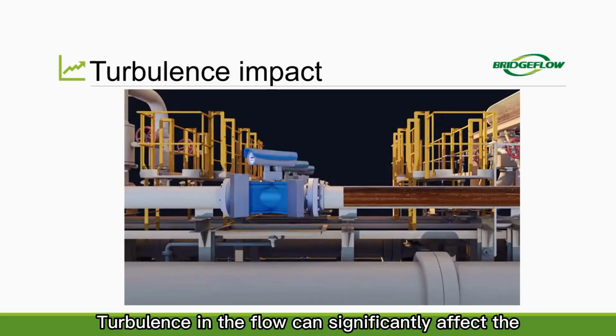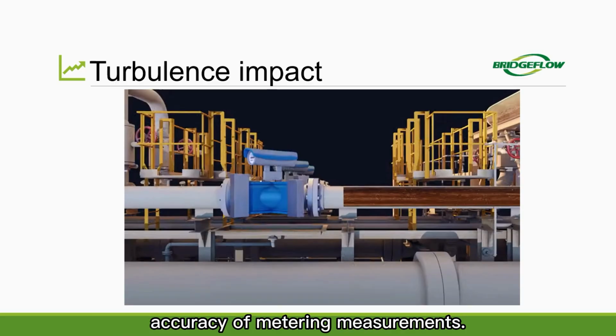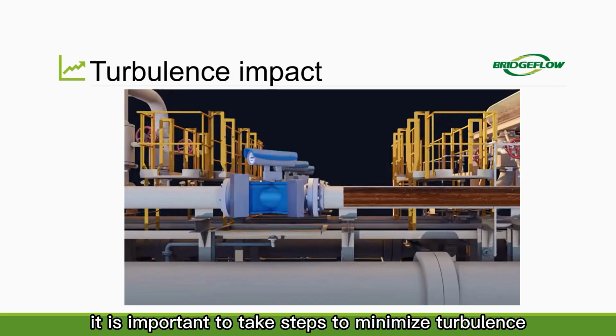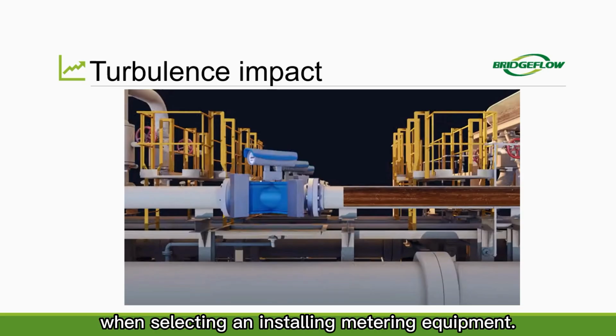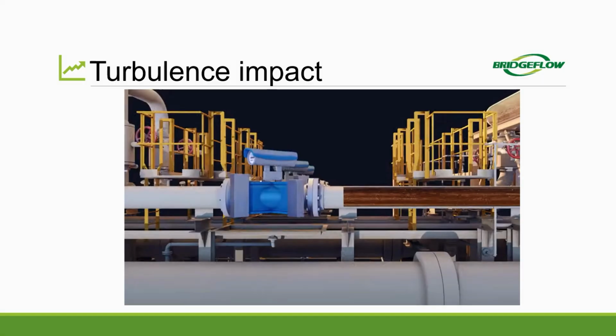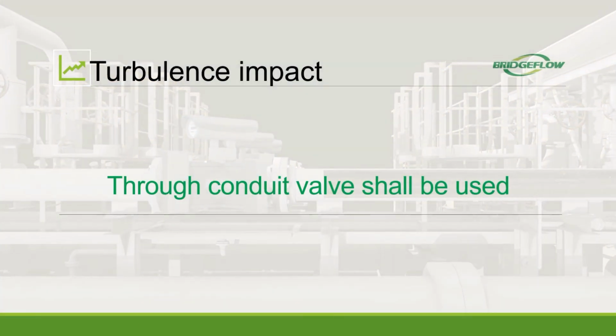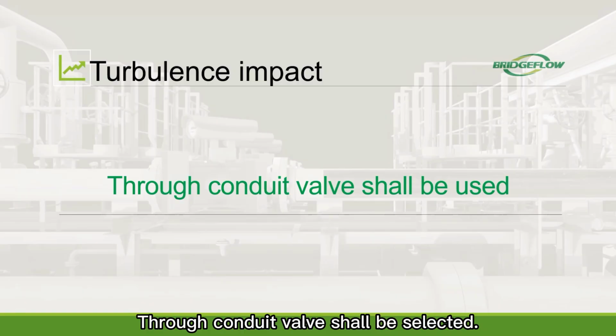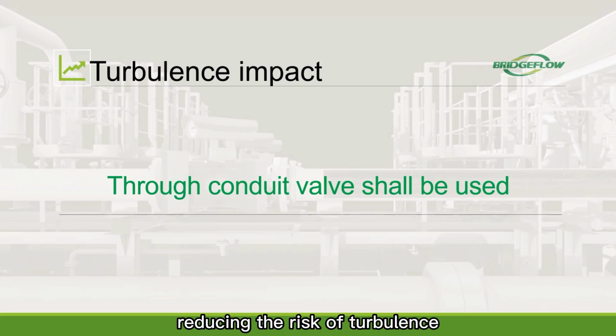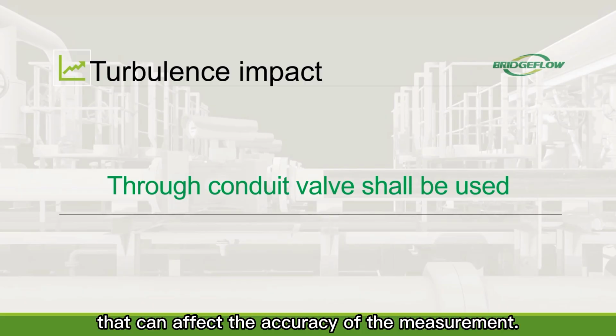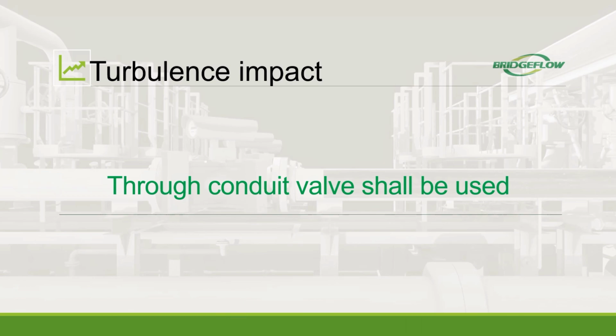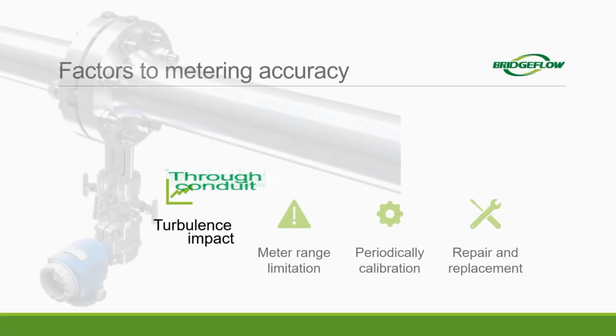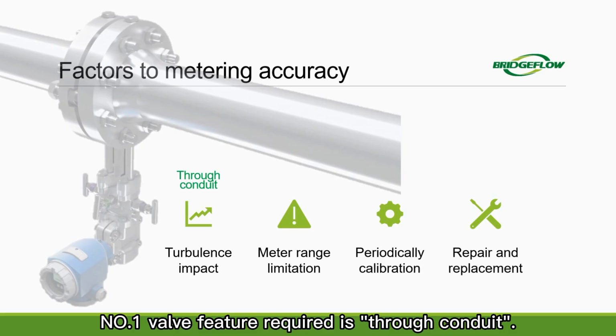Turbulence in the flow can significantly affect the accuracy of metering measurements. Therefore, it is important to take steps to minimize turbulence when selecting and installing metering equipment. Through conduit valve shall be selected. These valves allow the fluid to flow straight through the valve port, reducing the risk of turbulence that can affect the accuracy of the measurement. Number 1. Valve feature required is through conduit.